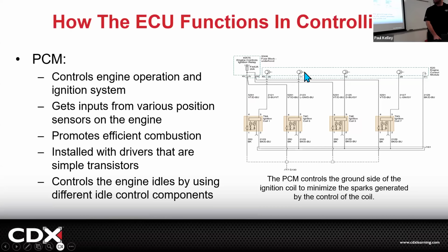Because if you're telling me you think it's got a bad transistor, a bad driver inside the ECM, I'm going to say why. And you'd say, well, I checked for voltage on 3 and it didn't have it. Did you check for voltage on 30? Yeah, and it didn't have it. Did you check 11? Yeah, that one was pulsing. Well, that's kind of weird. Yeah, if 30 is not pulsing, it could be that transistor.